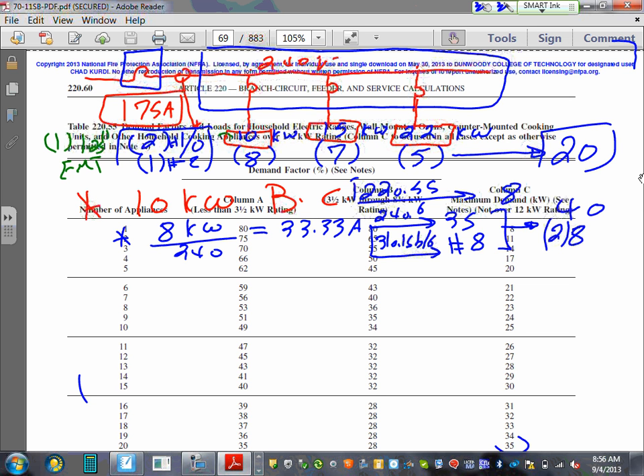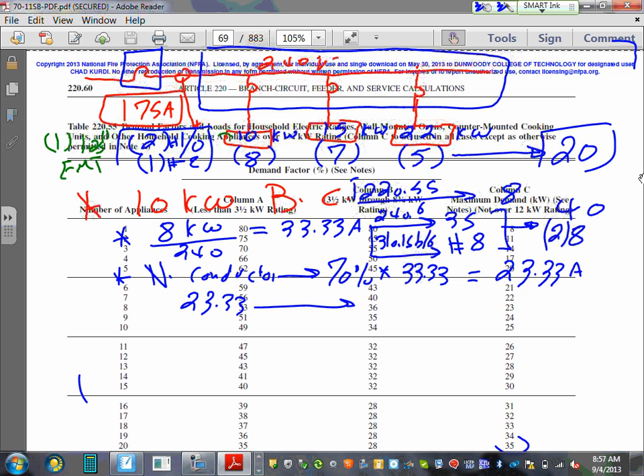Now, 2 conductors number 8. I'm going to size the neutral conductor. For the neutral conductor, guys, they allow you to take 70% of the 33.33. Can you guys give me 70% of 33.3, please? How much? 23.33. Thank you. 23 amps. And then you take the 23.33 to table 310.15(B)(16). What would that give you? One conductor number 10. You can't go number 14.